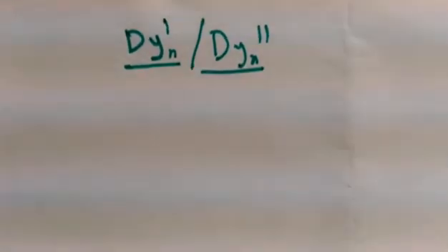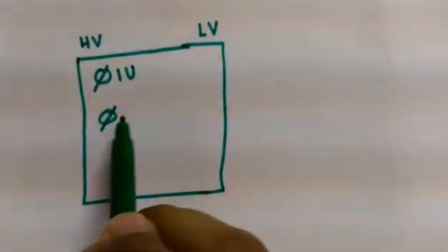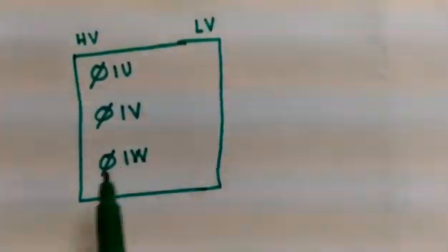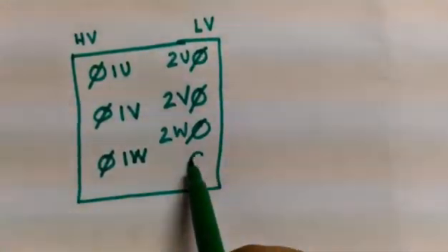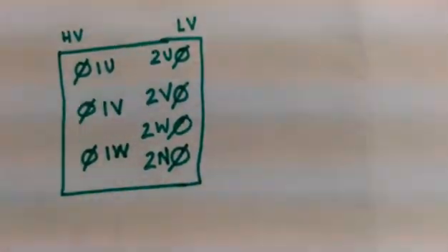So we have seen how to determine the vector group of a star-star transformer. Now in this portion we will see how to determine the vector group of a delta-star transformer. A delta-star transformer has two main vector groups: Dyn1 or Dyn11. The left-hand side is the high voltage with terminals 1U, 1V, 1W, and the right-hand side is the low voltage with terminals 2U, 2V, 2W, and 2N.